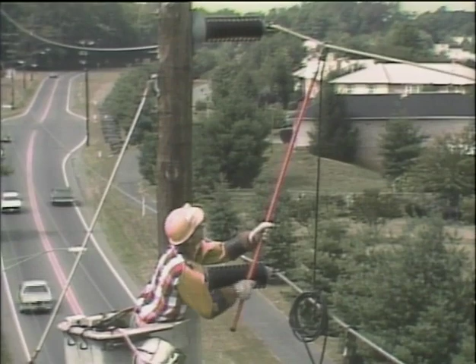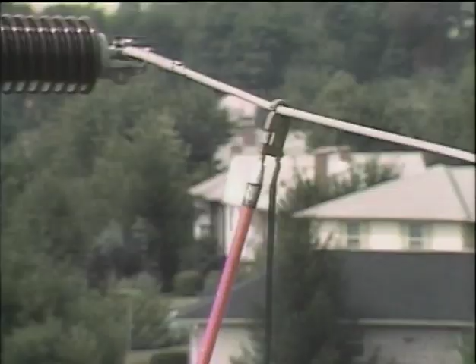When using a temporary ground on circuit lines, it's important to connect the jumper to an established ground before connecting it to a line. If you connected to one of the circuit lines first and the line became energized before you got a chance to connect the jumper to ground, you could receive a shock. For the same reason, you want to connect jumpers to the lines that are already grounded before you attach the jumpers to the other conductor lines. Once the circuit has been switched out, tagged, tested for dead, and grounded, the repair work can be done. You no longer need to worry about the lines becoming energized accidentally while you're working on them. When the job's completed, the grounds should be removed in the reverse order, the outside lines being disconnected first. The idea is to maintain a path to ground throughout the procedure.